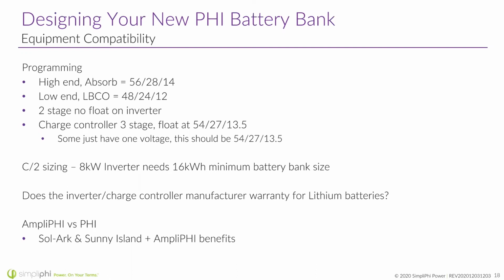One very important point here is sizing. So sizing should be C/2. We require you to have double the inverter's capacity in battery bank size. So if you've got an 8 kilowatt inverter, you're going to need 16 kilowatt hours in battery bank sizing. And that is a minimum, so you can always exceed that, but you cannot go under that, or you risk discharging and charging your batteries too quickly.